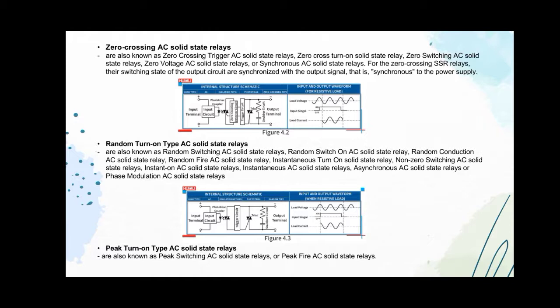The output circuit switching mode of the random type SSR relay is controlled only by the control signal, and it's independent of the power supply signal, asynchronous with the power supply. Random type solid state relays will be immediately turned on as long as there is an input signal at the input terminals, regardless of the state of the load voltage. Since the random solid state relay is turned on or off at any phase of the AC power source, a large interference signal may be generated at the turn on instant. This is figure 4.3 of the random turn on type AC solid state relay.